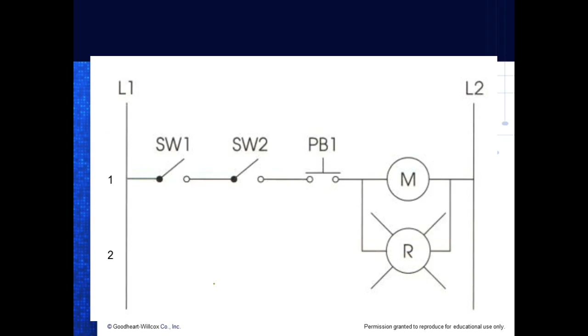Now your PLCs are going to do something a little strange, because you've only got so much display space. Well, what happens when your rung gets too long? It's going to come over here and put it in kind of an S shape like this. But all that is the extension of that line. And that way you get another line number. That's just the way the PLC does it because it doesn't have enough room to put everything in the line.